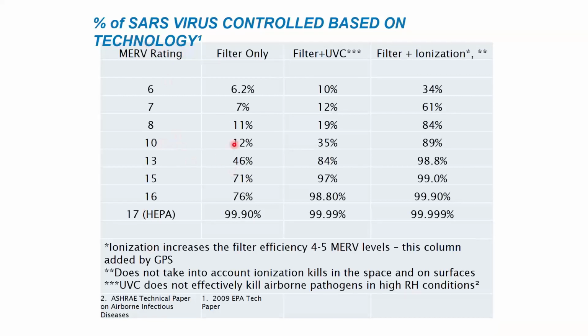But how much of those things, which are pretty similar in size to SARS-CoV-2 that we're concerned with - let's say Merv 10, I'm catching 12% of them. Merv 13, I'm catching 46%. Merv 16, 76%. If I go to HEPA, I'm getting 99.9% of these small things. So the higher my Merv rating, the more of these small things I'm going to collect, which is why the Ashrae recommendation was a minimum of Merv 14, although they noted to use Merv 13 if you can't handle the pressure drop of Merv 14, to start catching coronaviruses, including SARS-CoV-2.